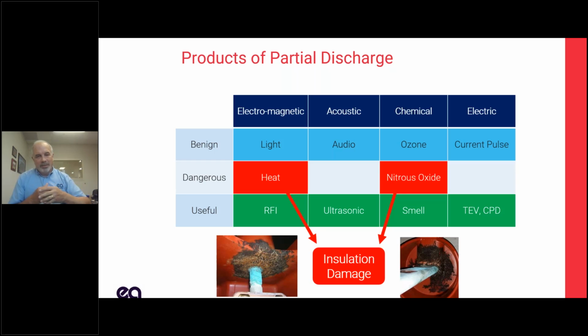Continuing down the electromagnetic spectrum, we've got RFI, or radio frequency interference. This is really useful. If you've ever been in a car in a lightning storm with the radio on and you hear the sparking and that comes through the radio, that's kind of how we detect partial discharge. Sparks generate a lot of radio frequency interference. They create a lot of broadband, and we can use that to detect PD.